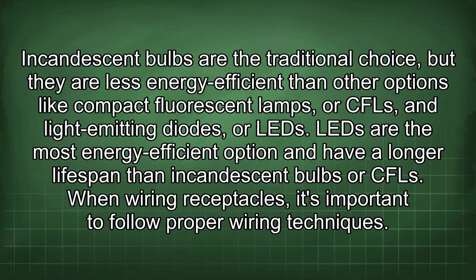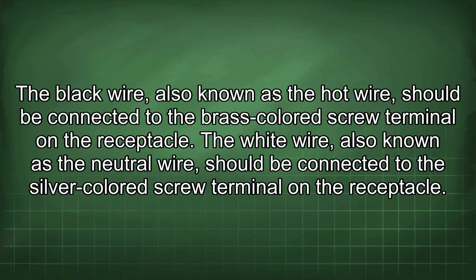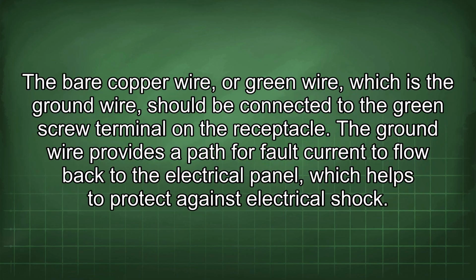When wiring receptacles, it's important to follow proper wiring techniques. The black wire, also known as the hot wire, should be connected to the brass-colored screw terminal on the receptacle. The white wire, also known as the neutral wire, should be connected to the silver-colored screw terminal on the receptacle. The bare copper wire, or green wire, which is the ground wire, should be connected to the green screw terminal on the receptacle. The ground wire provides a path for fault current to flow back to the electrical panel, which helps to protect against electrical shock.